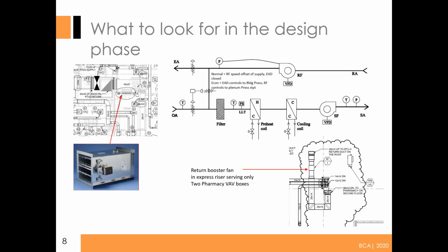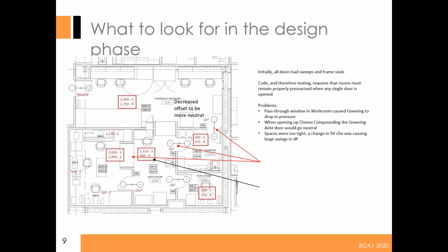Another thing that happens is when you try to put a pressure control room into an existing building. Often on this project, they had a non-ducted return system on multiple floors. So they're bringing the air back to a shaft, and they tried to put in a pharmacy and they couldn't control the pressure. What we ended up doing was putting in basically a return VAV box at the shaft so you can control the pressure from that room, and then added some exhaust fans for just the pharmacy. So it can be done.